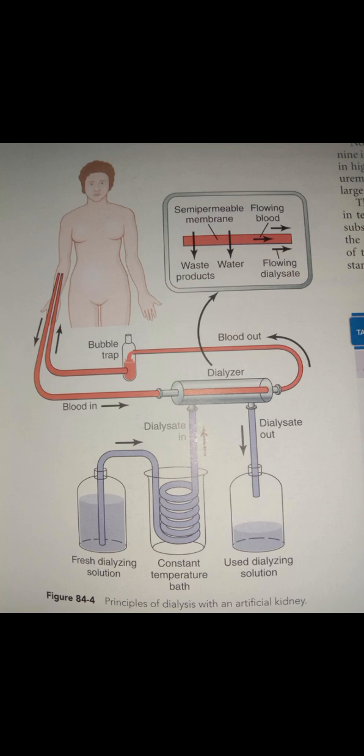In addition to diffusion of solutes, mass transfer of solutes and water can be produced by applying a hydrostatic pressure to force the fluid and solutes across the membrane of the dialyzer. Such filtration is called bulk flow or hemofiltration. Dialyzing fluid. Constituents in a typical dialyzing fluid include electrolytes like Na+ and K+, and non-electrolytes like glucose, urea and creatinine. Note that the concentrations of ions and other substances in dialyzing fluid are not the same as those in normal plasma or in uremic plasma.